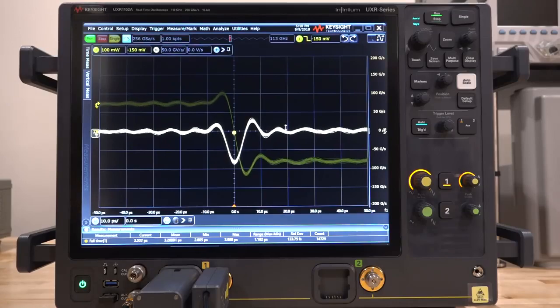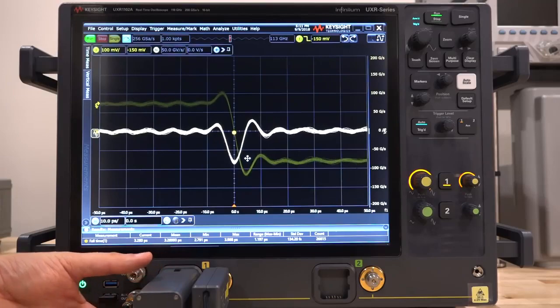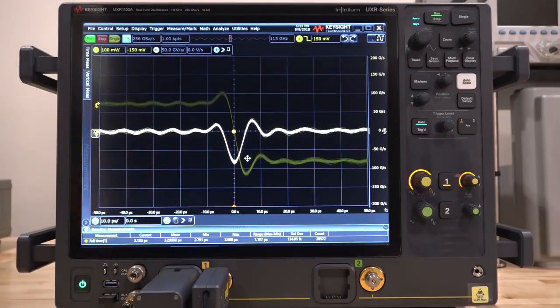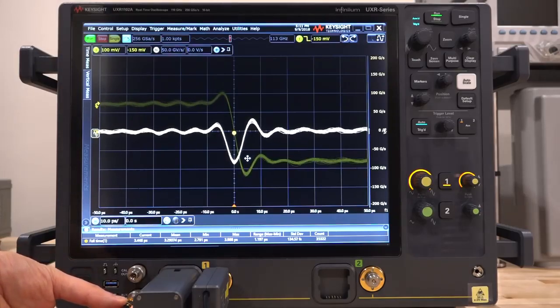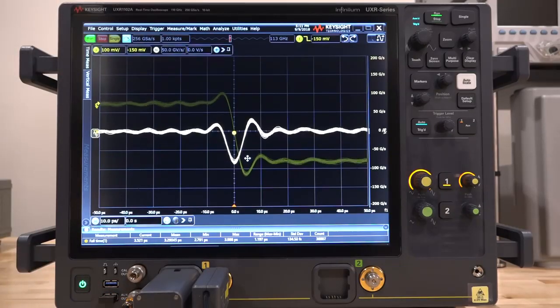Each calibrator can be a little bit different, but you can still perfectly calibrate the scope as long as there is a certain performance that each calibrator meets. And you can see the ripples here. And look at this impulse response here. This is in gigavolts per second. That's how sharp this edge is. It's amazing to see this. And this is a really good way to quickly do this. And not only can you do the calibration for the phase, group delay and frequency response of the channel itself, this also aligns the channels to each other, which is another important thing, because you have a single source coming in, and that source is self-aligned to all the channels, and that's how you can get everything calibrated to each other, which looks great.